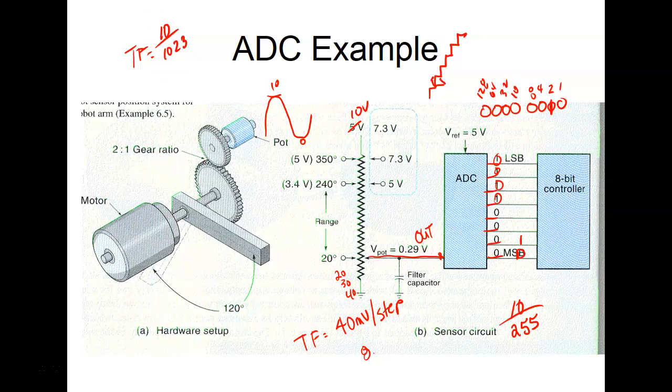We do that 10-bit. We get our calculator out, and there's a magic key on there called Y to the X. It might be X to the Y. Then you just type in 2, to the 10th. It gives you 1,024, minus 1 means you get 1,023 steps. With a bigger number of bits, subtracting the one would not make enough difference on a 12-bit A/D converter anyway, but this is the actual way we calculate these. If you've got a program control, you take that count and scale it to your function. Does that make sense?